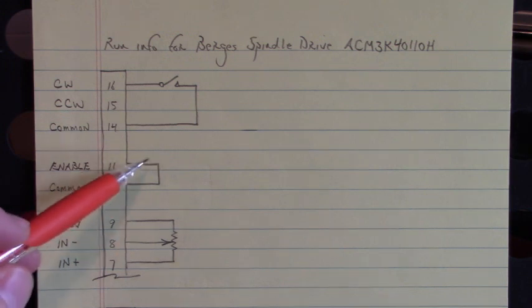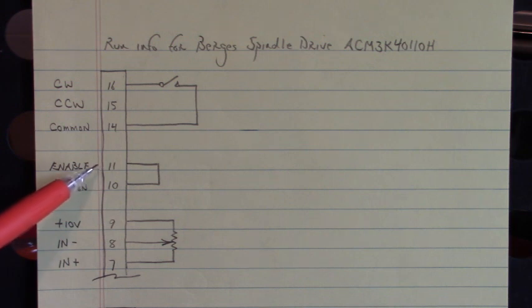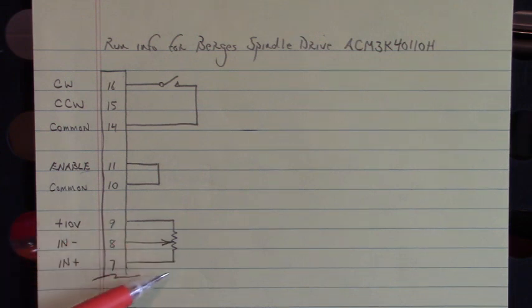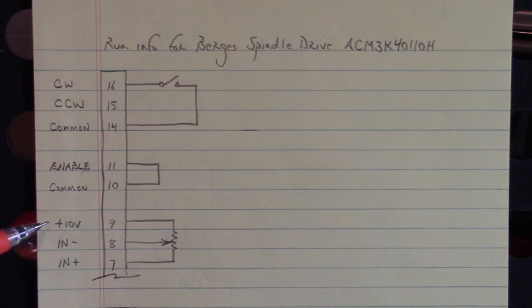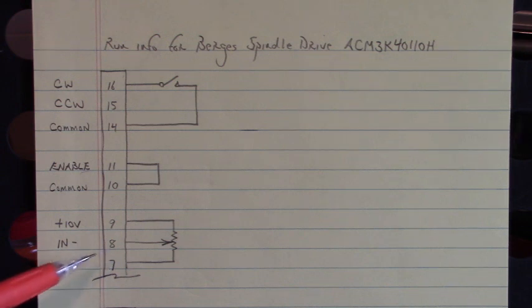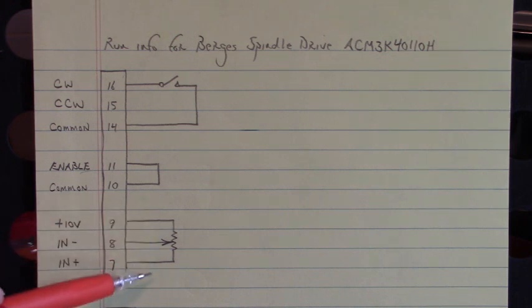Now, I had a switch at terminals 11 and 10 so that I could disable and enable that drive. Here is our speed reference input on terminal 8. We have on terminal 9 plus 10 volts, and down here on terminal 7 we have IN plus. On terminal 8, if we vary this voltage from 0 to 10 volts, we vary the speed that that spindle motor is run.